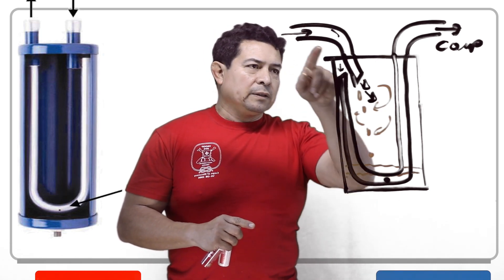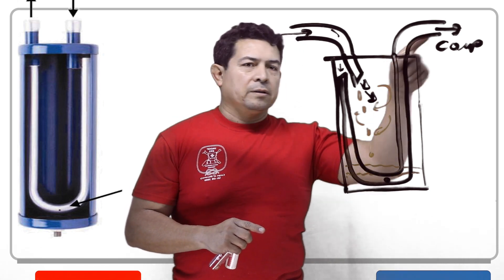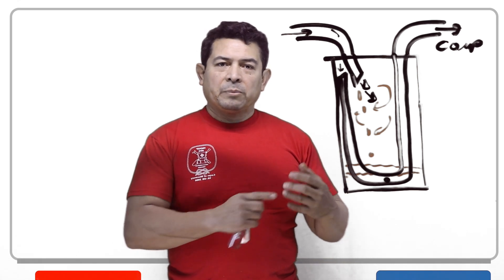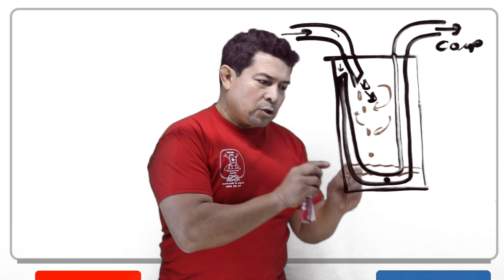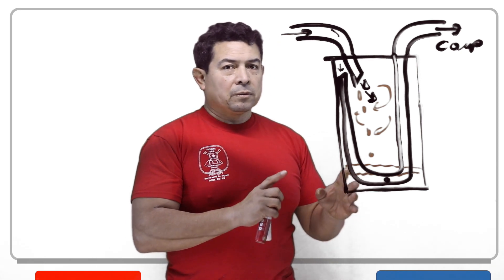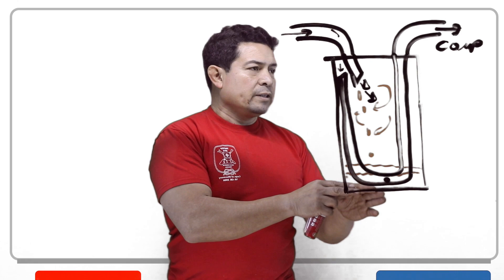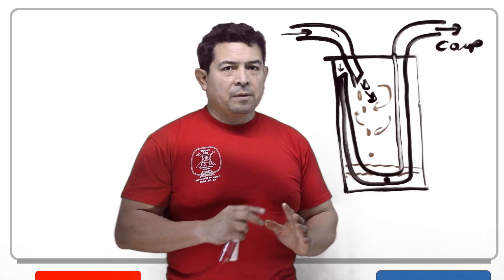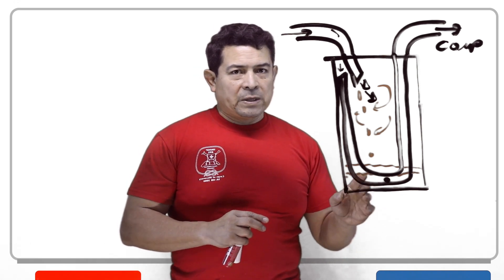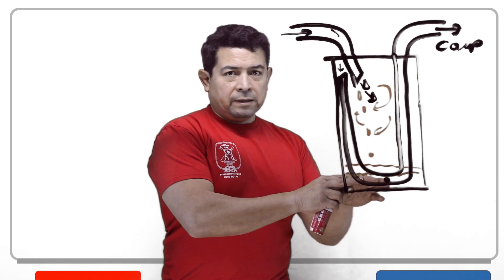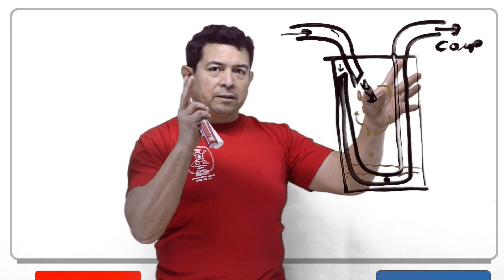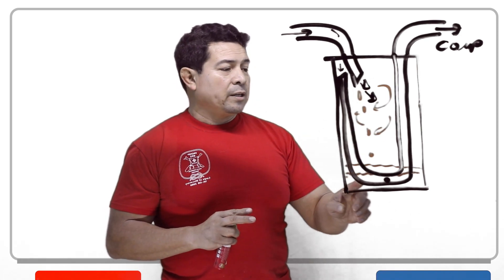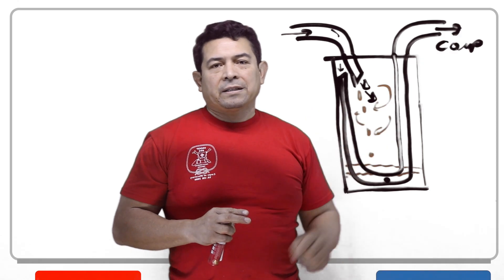This little port, because of the velocity of the refrigerant traveling through here into the compressor, is going to create a pressure drop right at that port. Now because of what they call a Venturi effect, it's going to draw the liquid in there — whether it's oil or liquid refrigerant — and send it back to the compressor. This orifice is specially made so that when liquid goes in there, it atomizes it, turning it into a fine spray, so you just have a mist going back to the compressor.